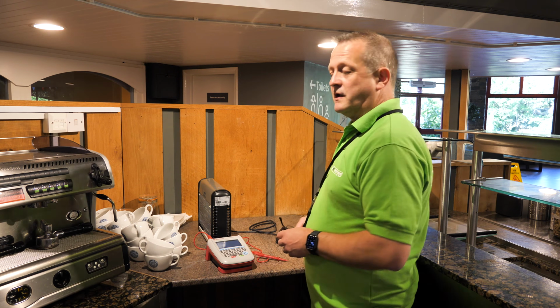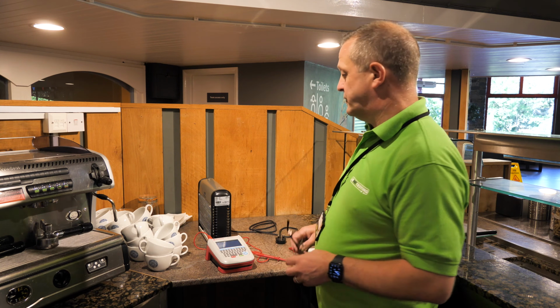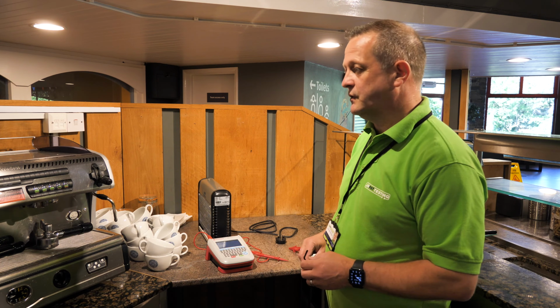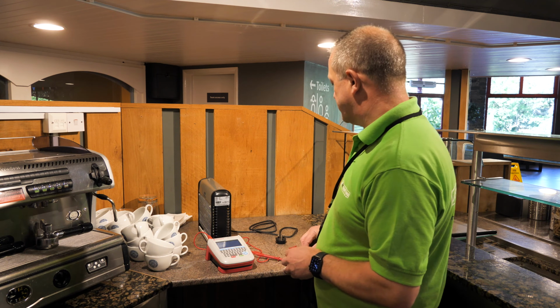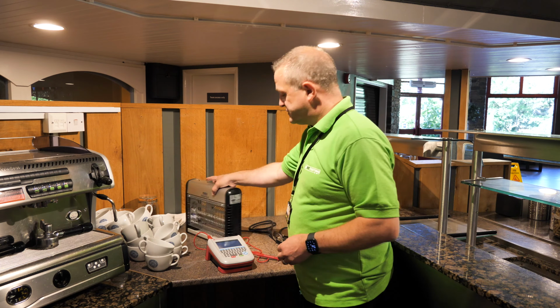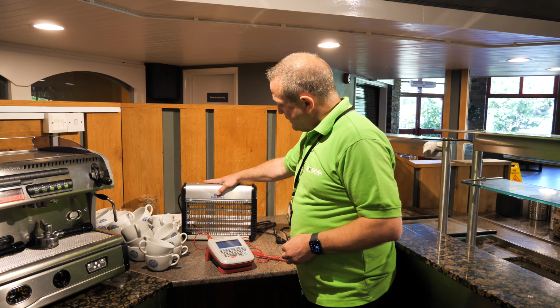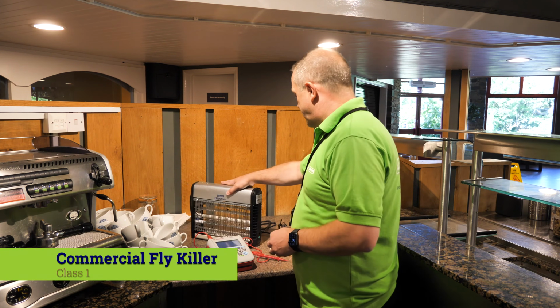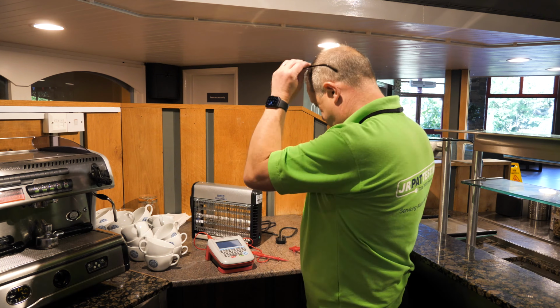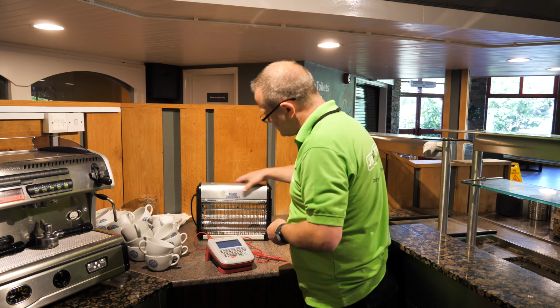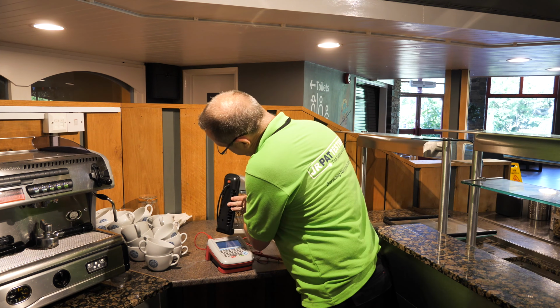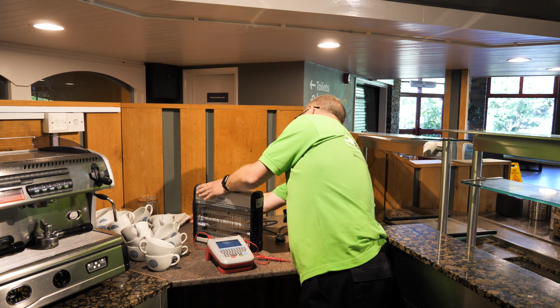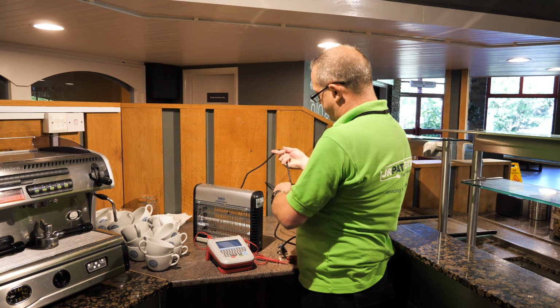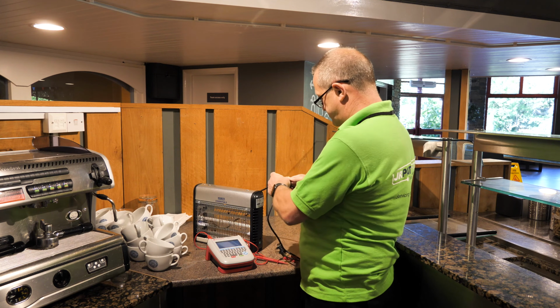So now we're going to look at a typical commercial kitchen with the various appliances that we have inside a commercial kitchen area. And first of all, we're going to examine the traditional fly zapper, which is a class 1 appliance. So the first thing we're going to do is a visual inspection, make sure that we're happy with everything. And we're going to look at the cable, make sure that none of the cables are exposed, no tears or cuts in the sheath.